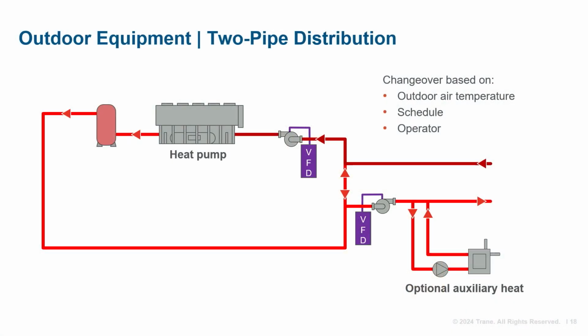With this type of system and a two-pipe heat pump and terminals, the changeover occurs at the unit. Prior to electrification, this may have been a chiller and a boiler piped and valved into a two-pipe distribution system. Here, an electrified system option is shown. The source of heat energy is from the ambient air. In this example, we have a packaged heat pump unit serving a two-pipe distribution system. The heat pump sees constant flow, and the pump likely requires two speed set points programmed into its VFD, as heating and cooling design flows may not be identical. The system is piped in a decoupled configuration with variable flow to the loads. Piping heat pumps in the primary-secondary configuration is common. It's simple, and operators understand it.